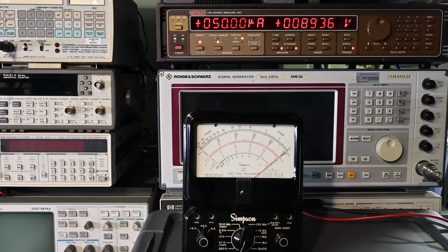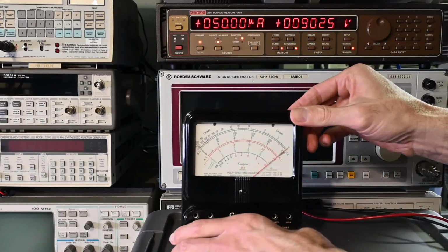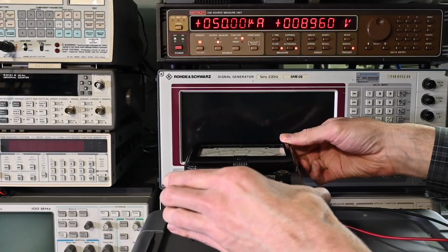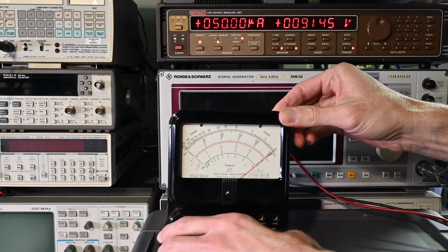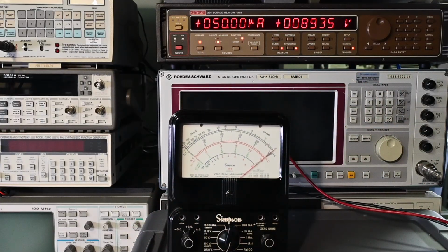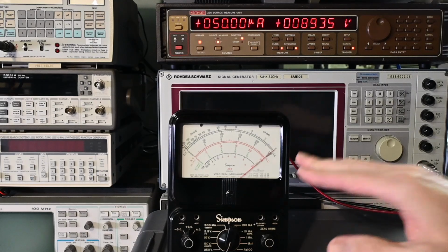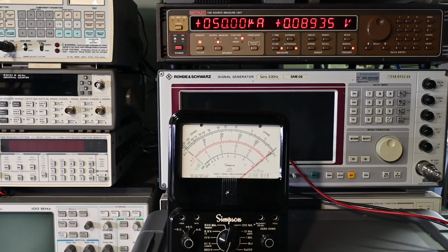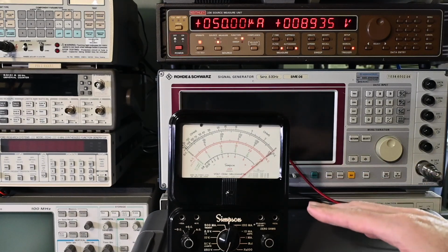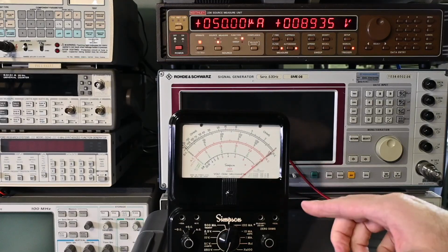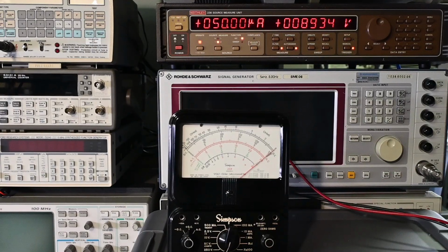What I'm going to do is move the camera out of the way, and then I'll be able to look straight on at the meter, and then as well lay it down like this and double check that it's reading accurately. But I think everything is looking very close at that point. So I'll just double check things off camera, and if it looks good, then I'll move on. I'll reconnect everything to the second adjustment with the 250 millivolts, and we'll adjust that potentiometer.